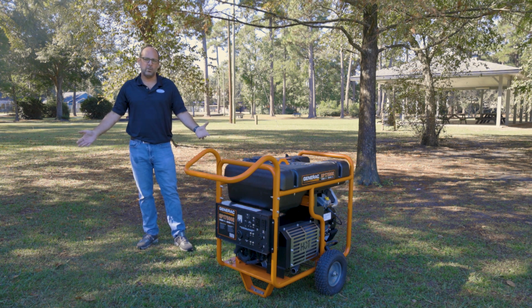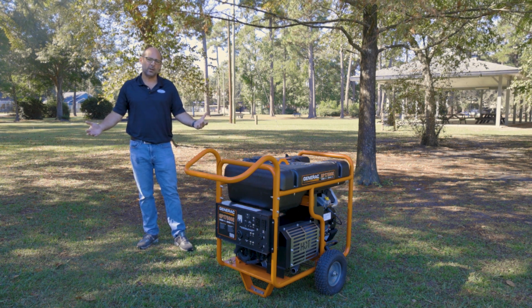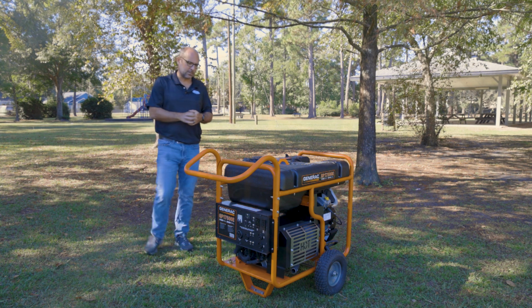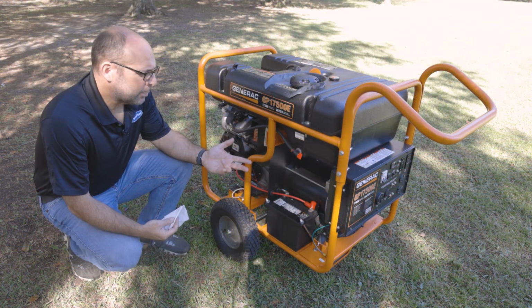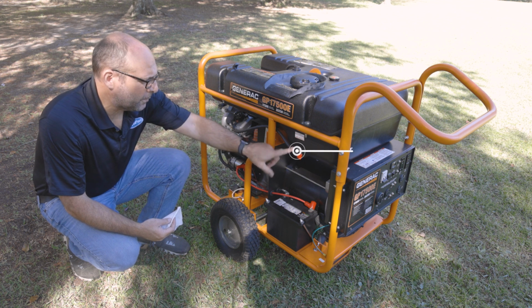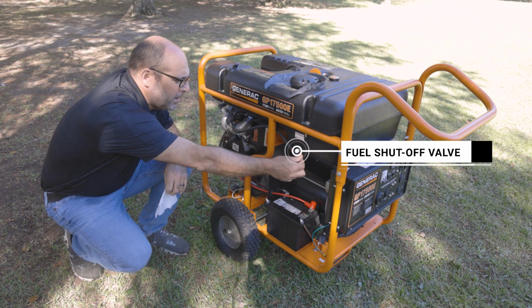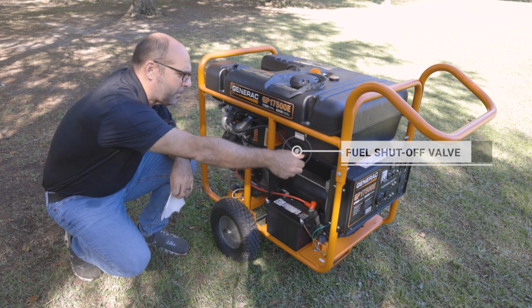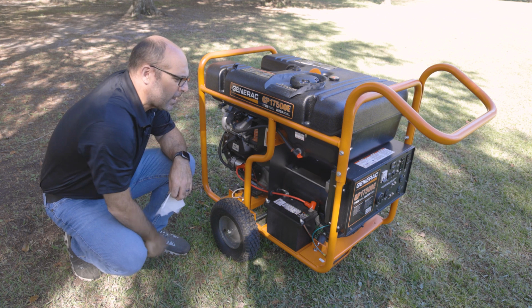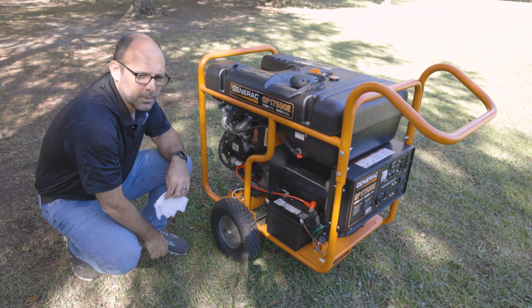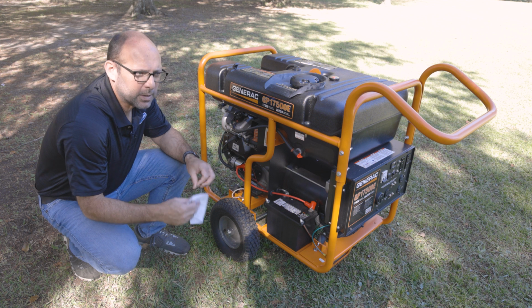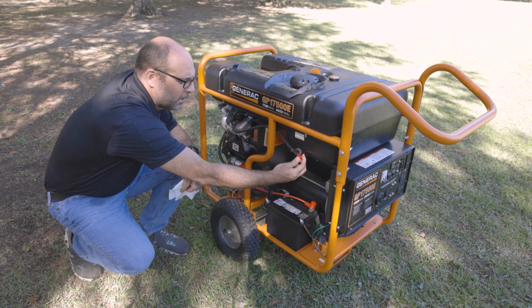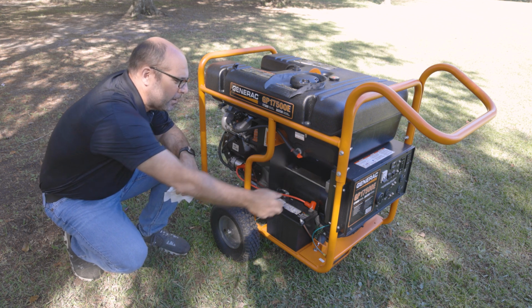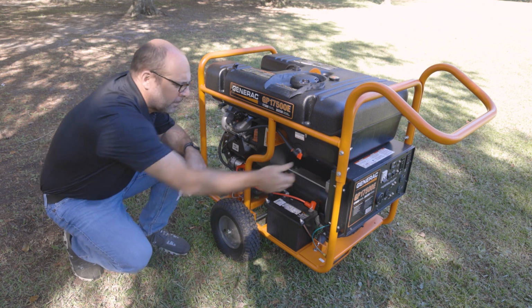Couple things you want to look at before you start your generator and get this thing hooked up to your tent system. On this side of the generator, we got a couple things to take a look at. One is the fuel petcock here. In the vertical position, that is the off position. If you rotate it to the side, that is now on. So before you fire up the generator, you're going to want to make sure that the fuel position is in the on position. Again, off and then on. Leave it off for now.